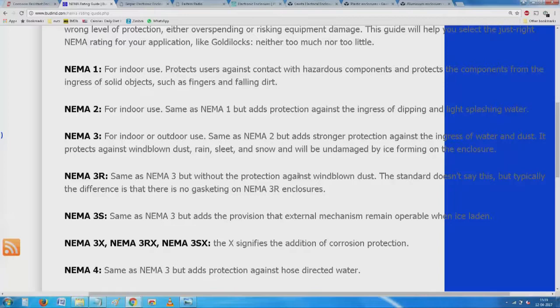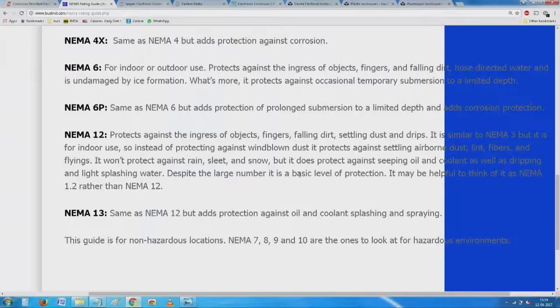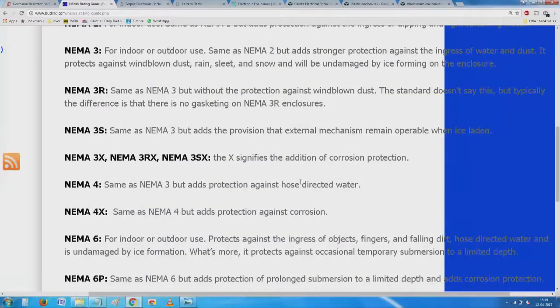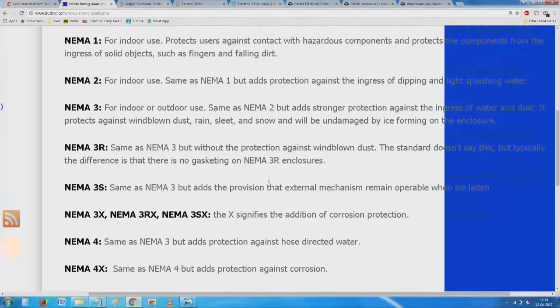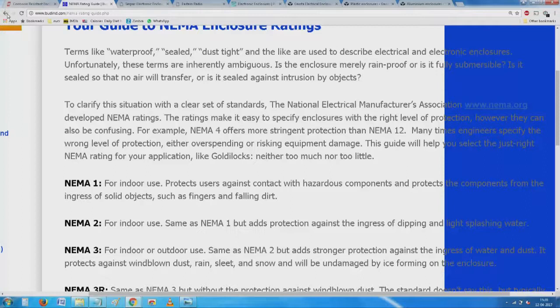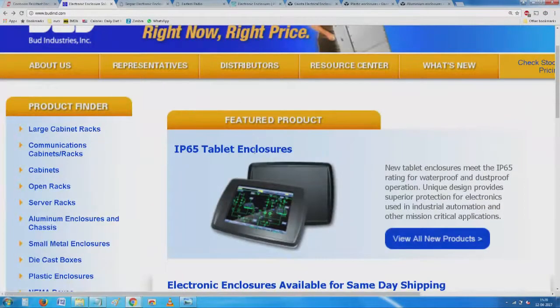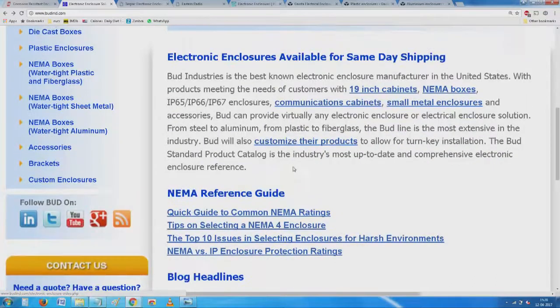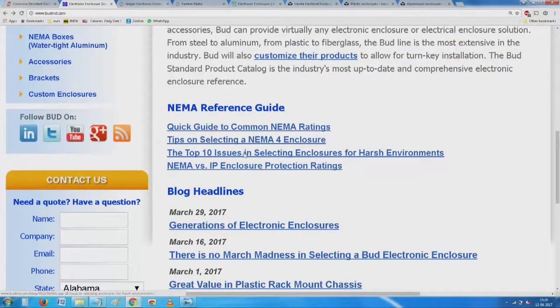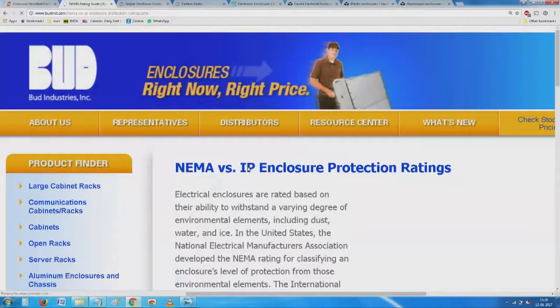The National Electrical Manufacturers Association (NEMA) provides classifications: NEMA 1, 2, 3, 4, 4X, and so on. Related to this is the IP classification — Index of Protection — which uses a two or three digit number system. Most of us are familiar with IP55, and then there are IP56, IP66, and IP67. Going through these in detail, you'll notice it's not as simple as just buying a small box.